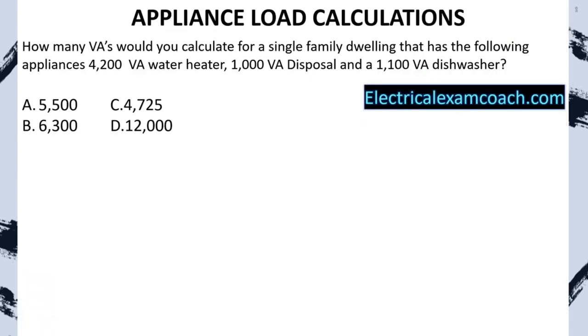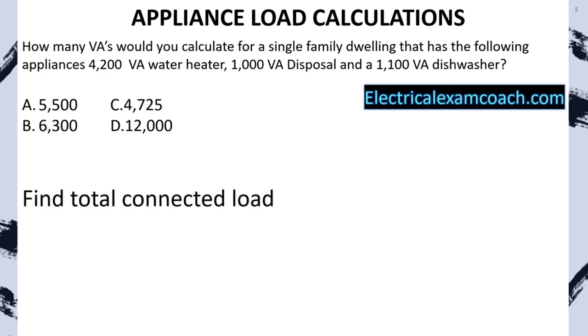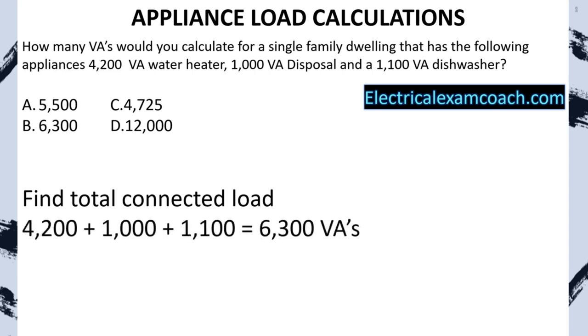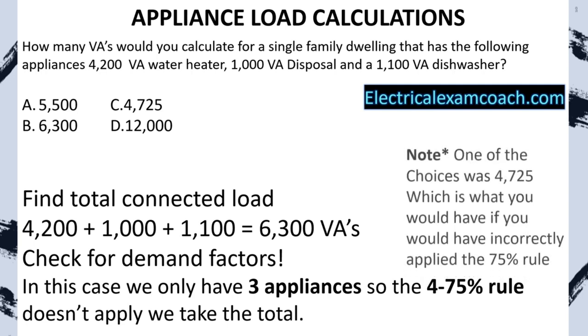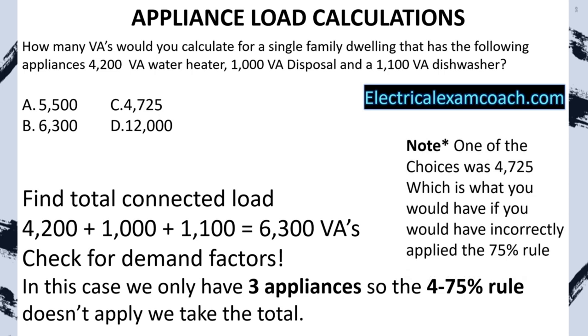Practice problem: How many VAs would you calculate for a single-family dwelling with a 4,200 VA water heater, a 1,000 VA disposal, and a 1,100 VA dishwasher? First, find the total connected load: totaling all up equals 6,300 VAs. Now check for demand factors — we only have three appliances, so the four-or-more 75% rule does not apply. We take the total connected load at 6,300. Note that one of the answer choices was as if you incorrectly applied the 75% rule — because we only have three, we don't apply any demand factor at all.